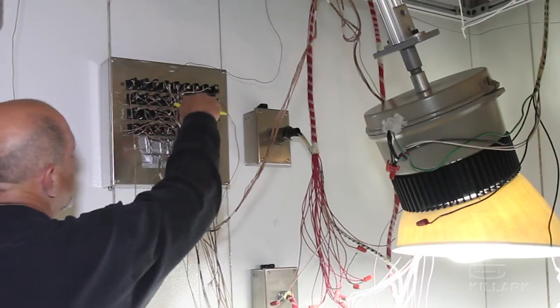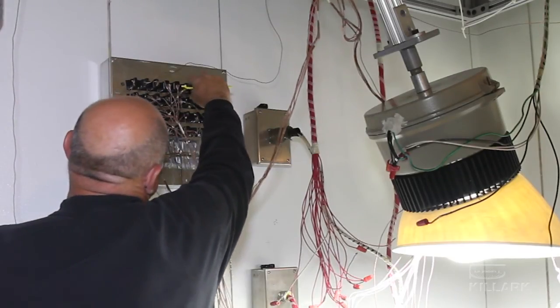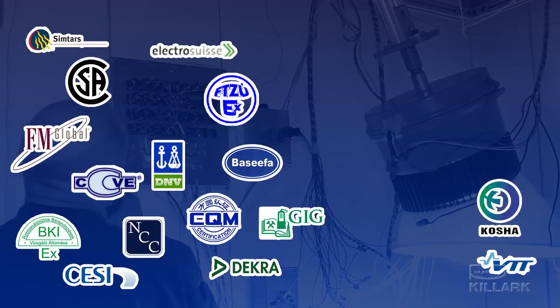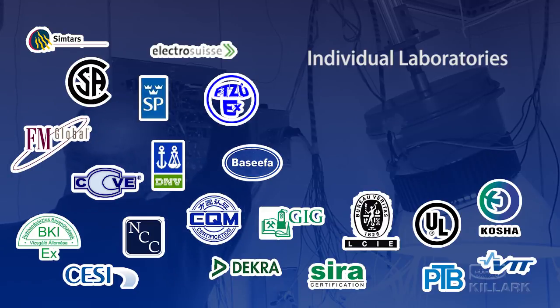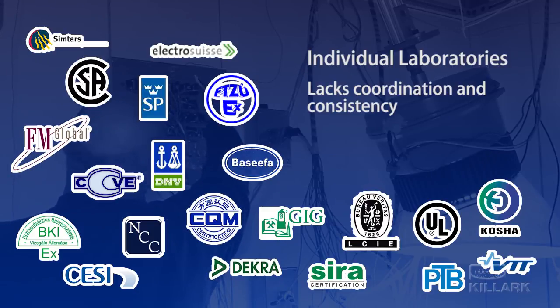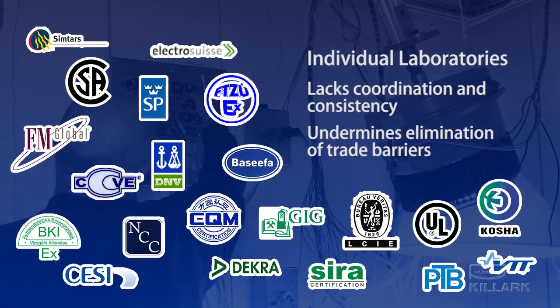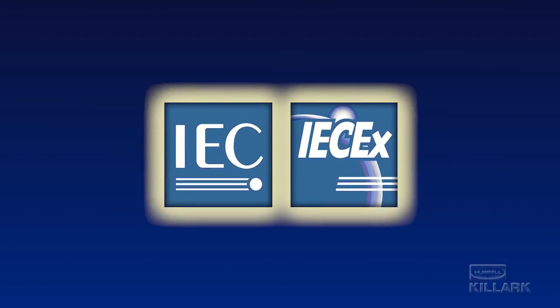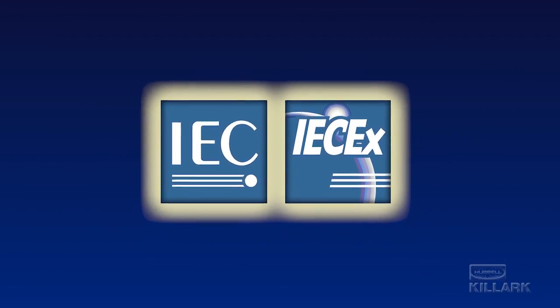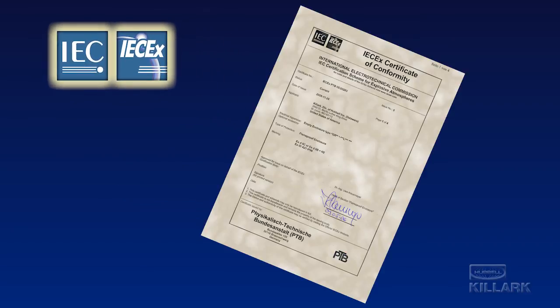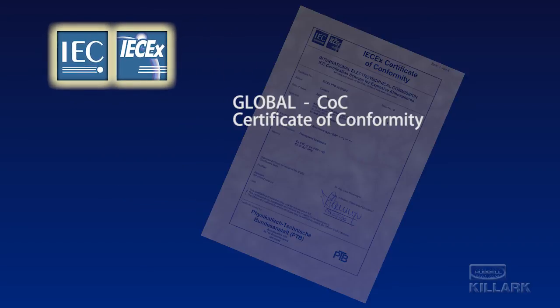Prior to the drive toward harmonization, each country's recognized laboratory developed its own set of testing protocols to evaluate products. But the problem with this individualized approach is that it lacks the coordination to provide consistent assessment criteria and testing, and that undermines the goal of eliminating barriers to the international trade of explosion-protected equipment. The IEC EX scheme was developed to address this issue. The intent of the plan was to be able to provide a single global certificate of conformity based on uniform testing and documentation procedures.